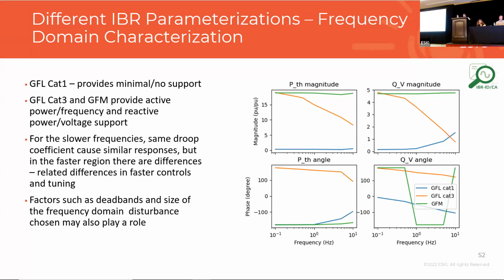As we move towards the right on that same first column, towards the higher frequency axis, we start moving towards the fast varying resource, the fast varying events that would occur. Here we start seeing category 3 dip a little bit in its response because there's a bit of delay in the control system being able to respond to the disturbance. But the GFM resource has a lesser amount of that delay. Again, category 1 does nothing at all.